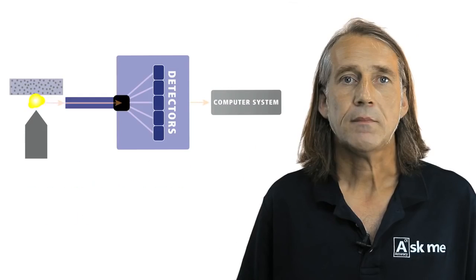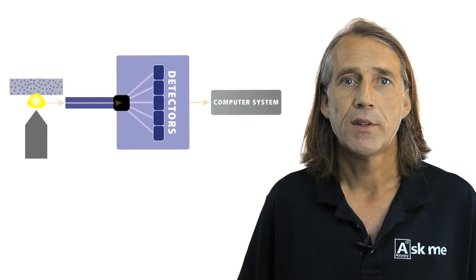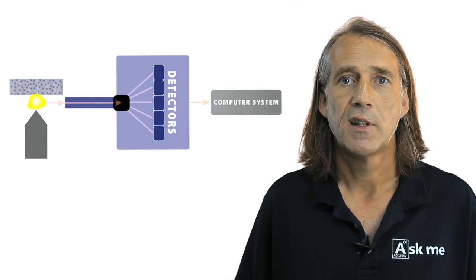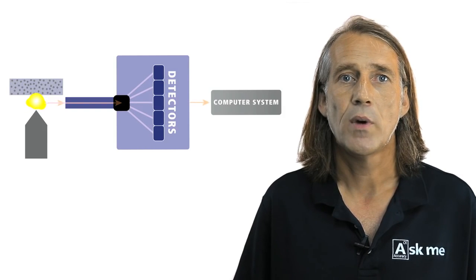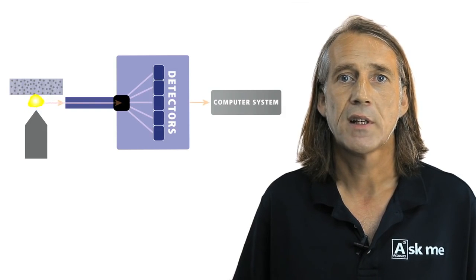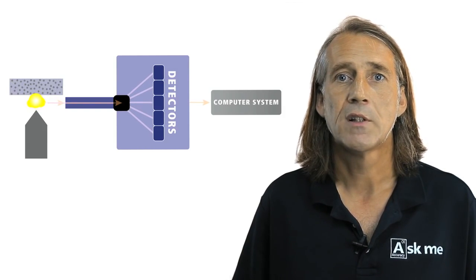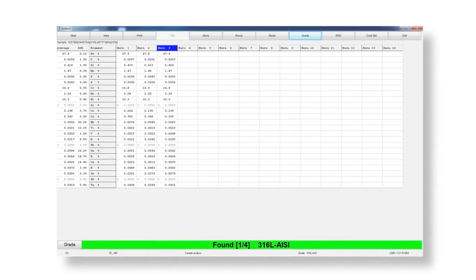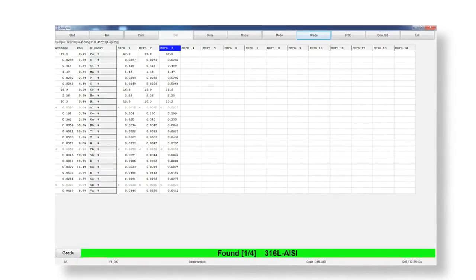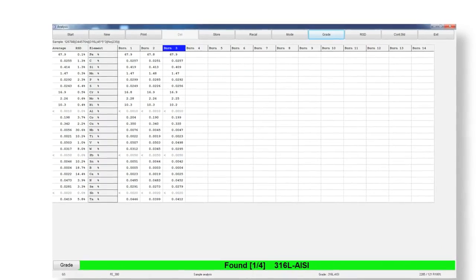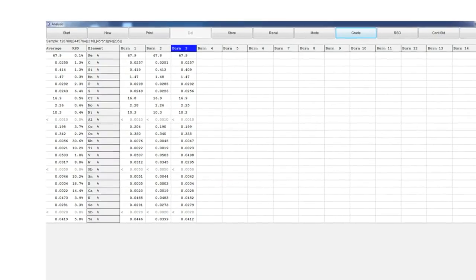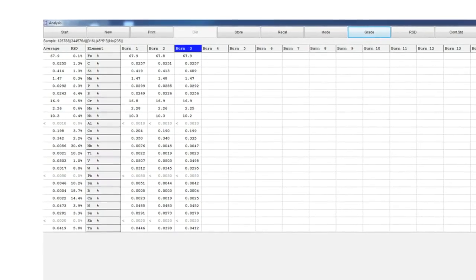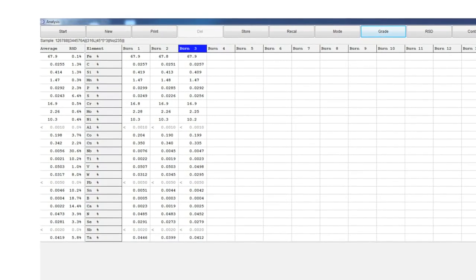The third component is a computer system. The computer system acquires the measured intensities and processes this data via a predefined calibration to produce elemental concentrations. The user interface ensures minimal operator intervention, with results clearly displayed which can be printed or stored for future reference.